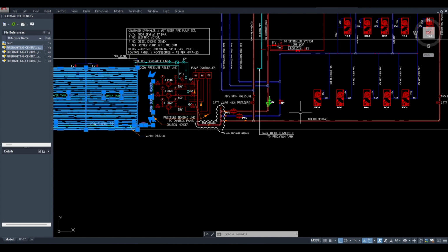Okay, and in some cases there is no water, that is a separate system. Okay, so don't mix it here. I'm talking about the 80% of the places that we deal with here in UAE and Asia. If it's not a freezing country like the US, then this is the system we mostly work with. Okay, so in that, ready-made water is always there. So these waters are pressurized water. Okay, and it has to be pressurized at a minimum of 6.9 bar. Okay, so it cannot be less than that. That is the rule. So suppose the pressure in the line is going down, then this pump should run again to maintain the pressure of the water inside these lines.